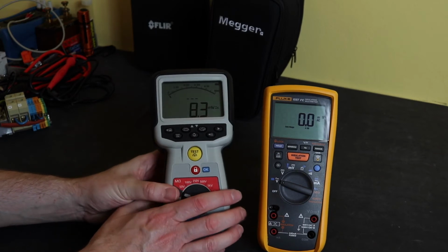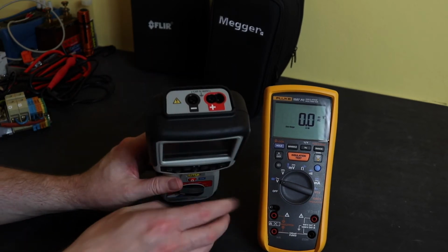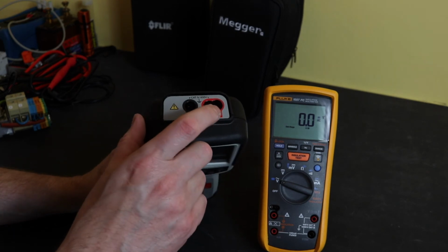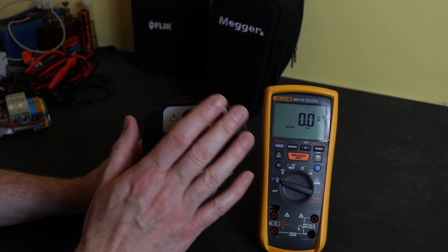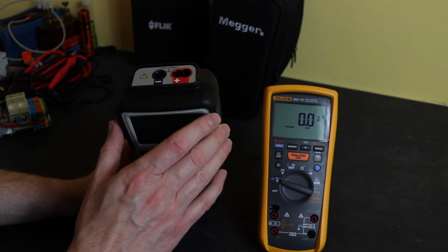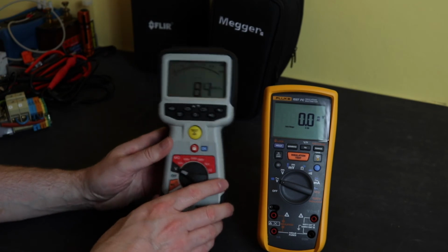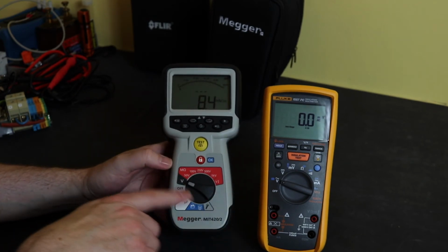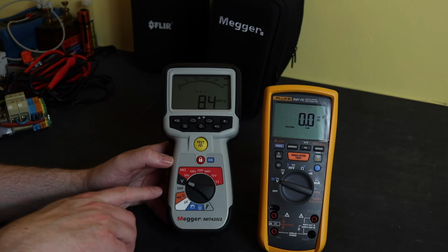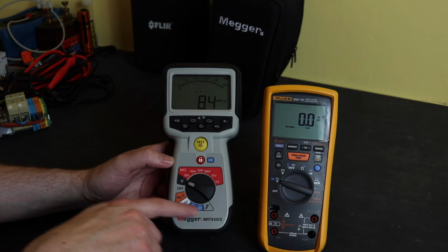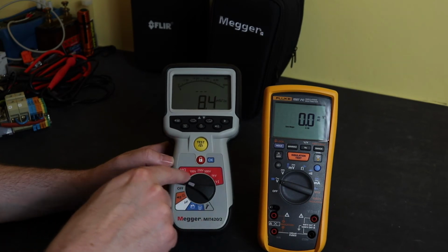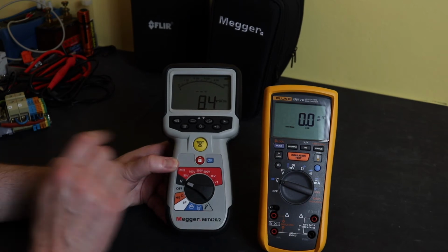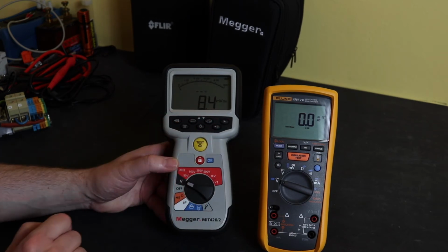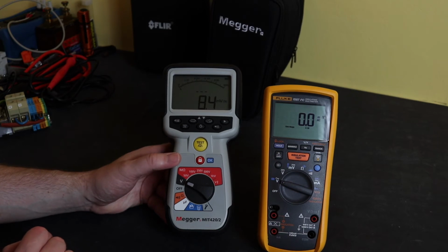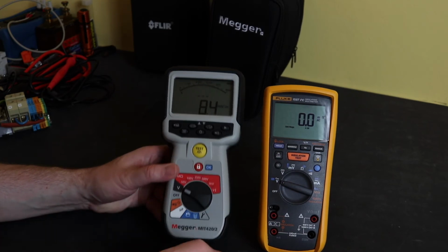And there's the front display there, the only two input jacks at the top here, that takes the remote probe, and then the standard 4mm there, and that gives you the test points for all the test functions. Cat 4 600 volt input protection, and then you have the standard rotary function switch, center off position, auxiliary functions around the bottom, then your voltage and insulation test functions along the top there, and then sub functions off of the menu buttons up there underneath the screen.